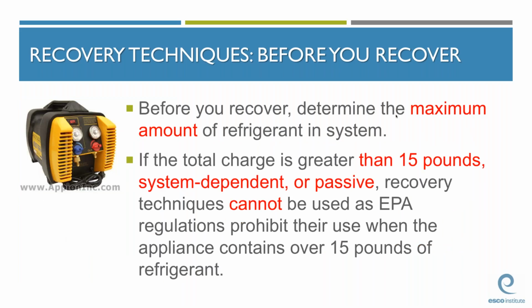Before refrigerant recovery from a system, be sure to determine the maximum amount of refrigerant that's contained in the system. If the refrigerant charge is greater than 15 pounds, system-dependent or passive recovery techniques cannot be used. This is because the EPA prohibits the use of these recovery methods on appliances that contain more than 15 pounds of refrigerant. So if the system contains more than 15 pounds, then technicians are going to need to use active recovery equipment to perform the recovery process.